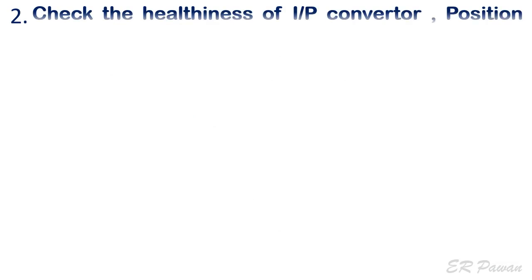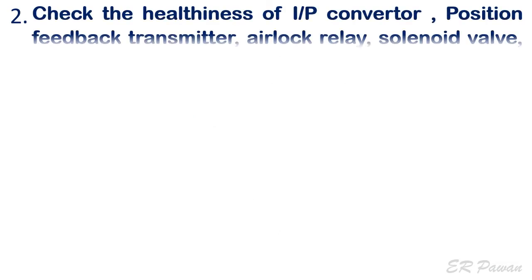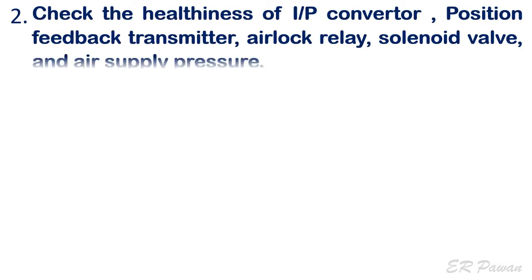Step 2: Check the healthiness of the IP converter, position feedback transmitter, airlock relay, solenoid valve, and air supply pressure.